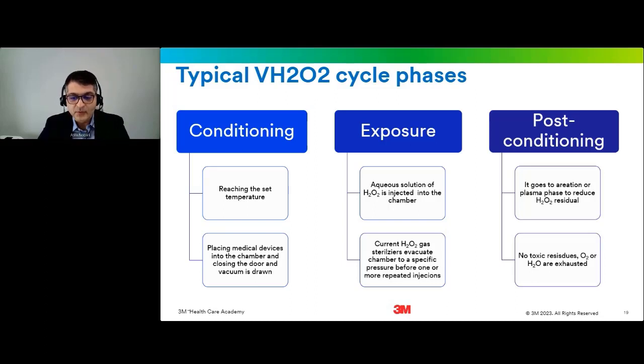It also can form cold spots under the load. As you know, cold spots are any location where the temperature does not achieve the minimum sterilization temperature during the sterilization process, so they can affect the efficacy of the process. In order to avoid cold spots, make sure the medical devices are visibly dry. You may use compressed air for lumen devices or use dry cabinets, and you need to follow the guidelines for them. Next phase is the exposure phase.